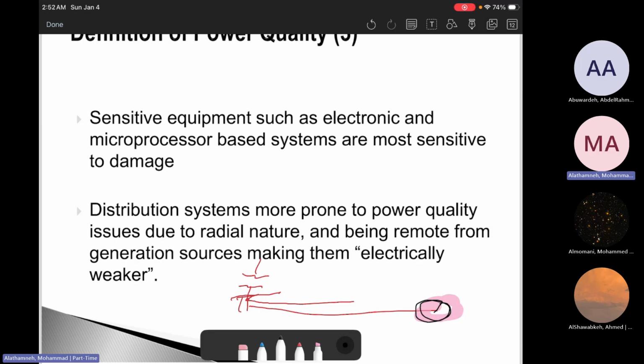Capacitor switching means turning shunt capacitors on or off, and all of that creates power quality problems. Again, the pumps, the compressors, anything with motors, they have high startup currents. This will cause some voltage drop, and especially if you are at the edge, the end customer, the voltage drop will be more significant, which will have a very big impact on these customers.